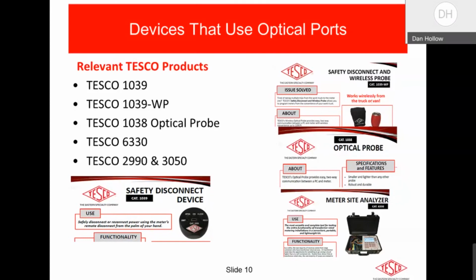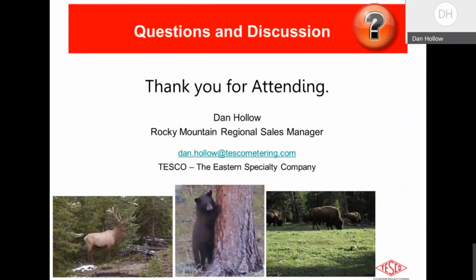What I neglected to mention, and this struck me a little too late as well, is that in the old days, before solid state electronic meters, and even before box recorders, but box recorders kind of came along at the same time as electromechanical meters equipped with pulse initiators. But before that, the pickups actually had to do two things. They had to fire a beam at the disc on a mechanical meter, and the beam either struck a black stripe of paint on the meter and didn't reflect back, so it didn't hit the phototransistor, which created a pulse, or there would be a hole in the disc, and that beam would go through the hole and hit the phototransistor on the other side, making a pulse.